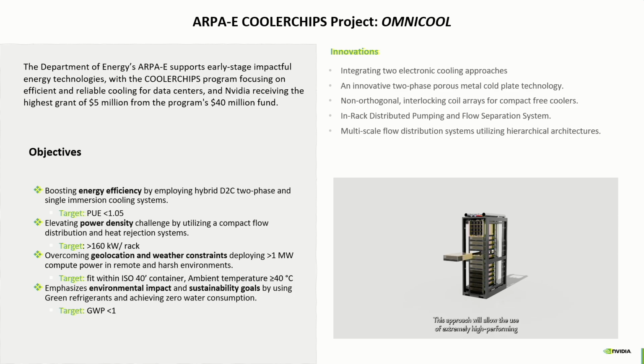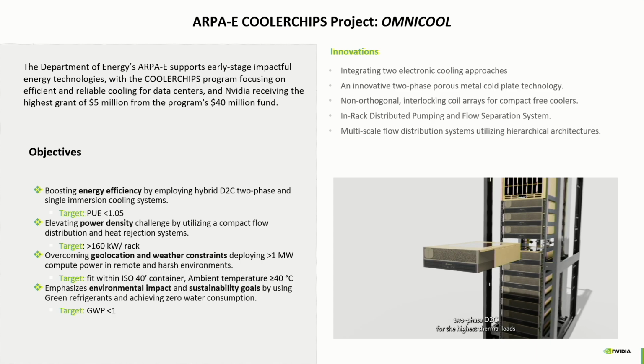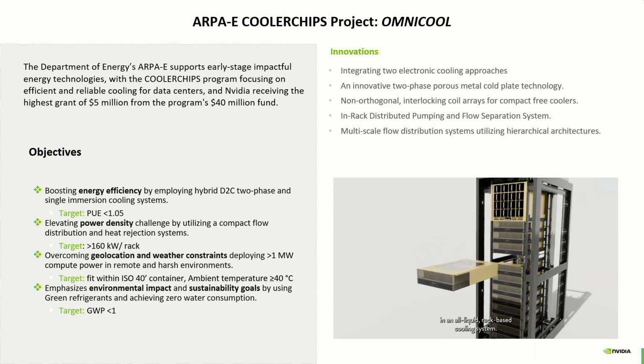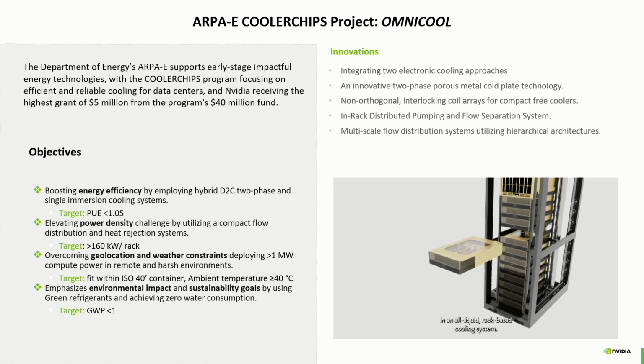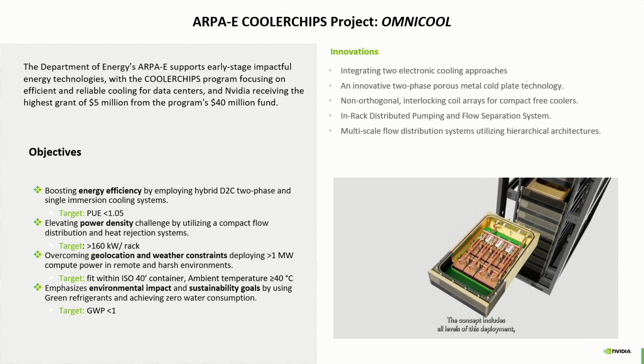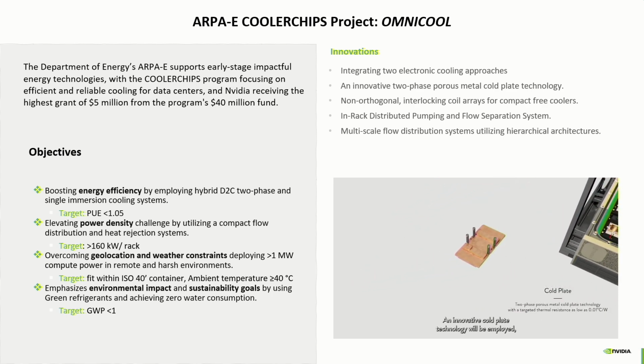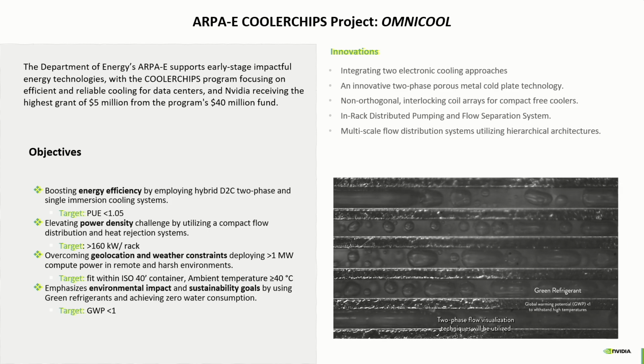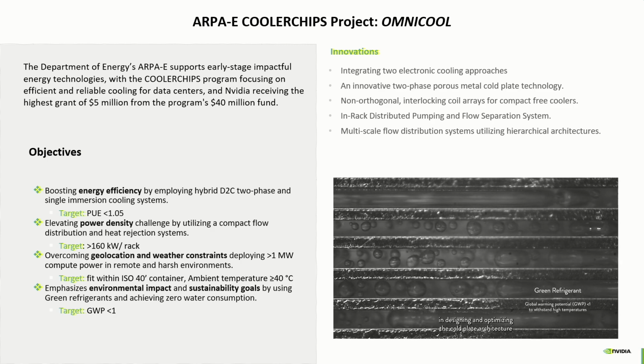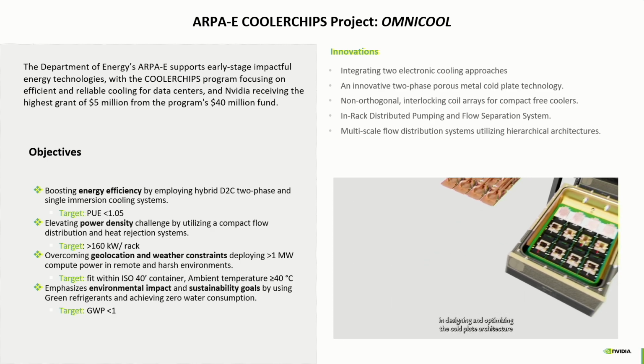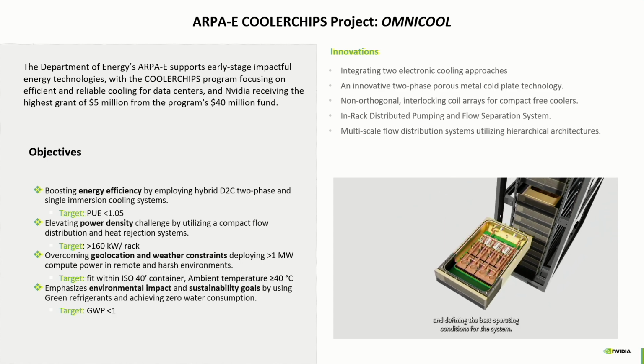This approach will allow the use of extremely high-performing two-phase direct-to-chip for the highest thermal loads in an all-liquid, rack-based cooling system. The concept includes all levels of this deployment, addressing all of the program objectives. An innovative cold plate technology will be employed, operating with a green refrigerant. Two-phase flow visualization techniques will be utilized in designing and optimizing the cold plate architecture and defining the best operating conditions for the system.